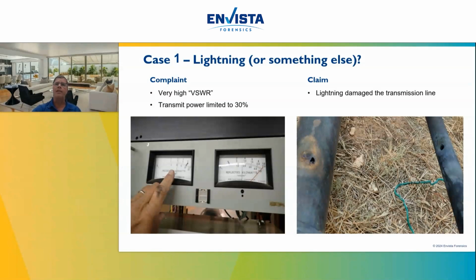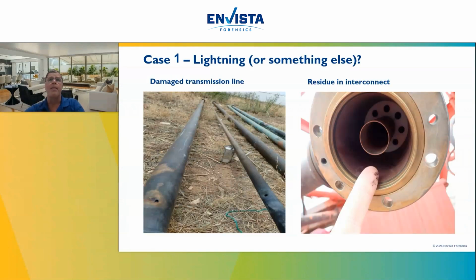Here's a couple of pieces that they showed. These were actually replaced prior to Envista coming to the site. There were a few sections like this. We'll get an overall look at these pieces in a second, but these are components, part of a transmission line. They're just a couple of copper tubes, as we see here, looking into the end of one of these. We have an inner copper tube and an outer copper tube there on the right. You see a finger there that has just picked up a little bit of soot from the inside of this installation.